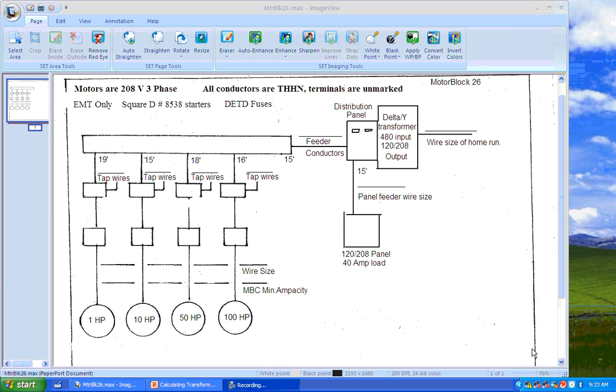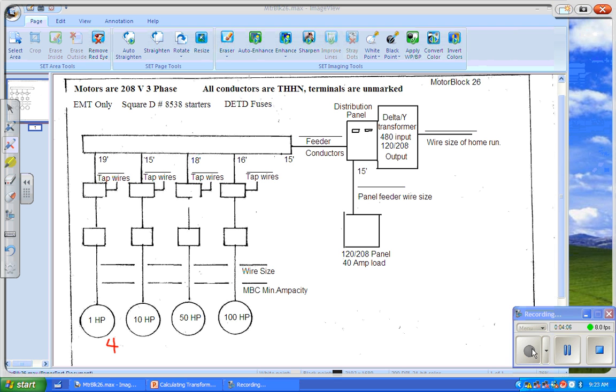Okay, so our 1 horsepower, the FLA, is 4.6 amps. Our 10 horsepower is 30.8. Our 50 horsepower is 143. And our 100 horsepower is 273. Now, if we were doing our wire calculations and everything else, we would go up and take 125% of each one of those, and we would find our motor branch circuit ampacity. But for this case, we don't need to do that. We do need to do this for the biggest motor, because you know that if we're going to find the minimum ampacity of our supply circuit, we need to take 125% of our biggest motor.